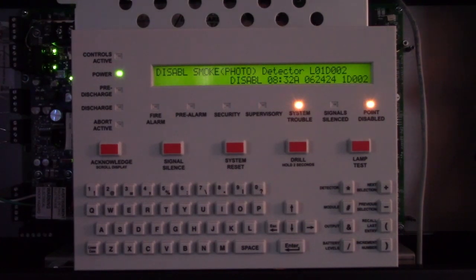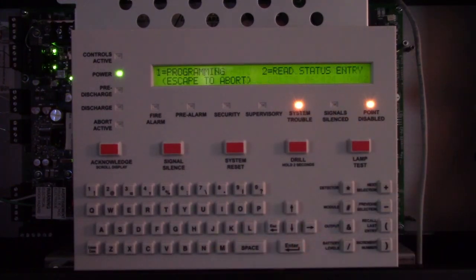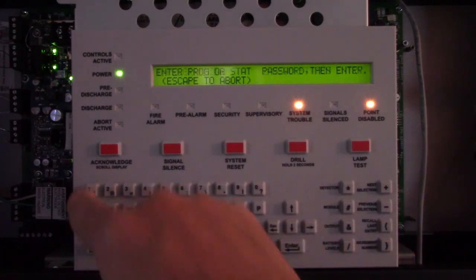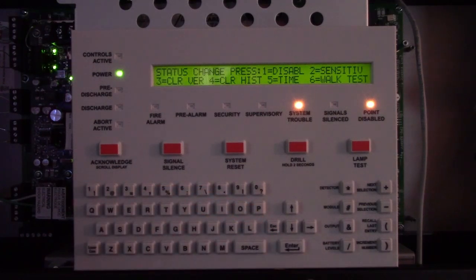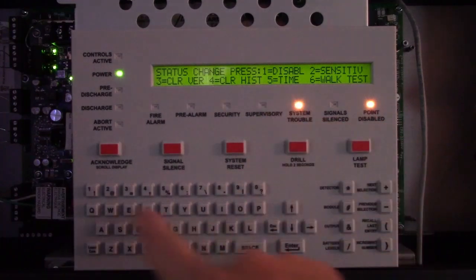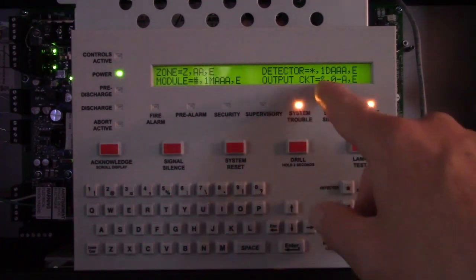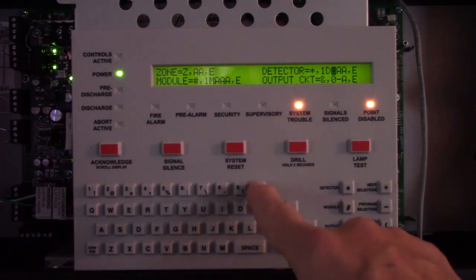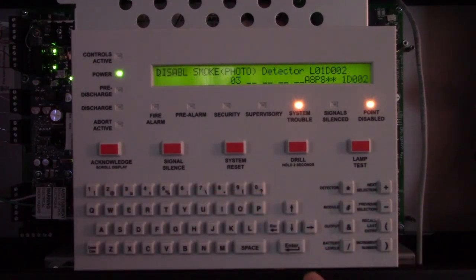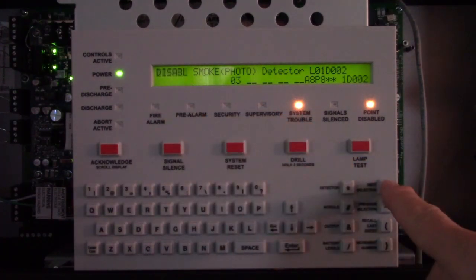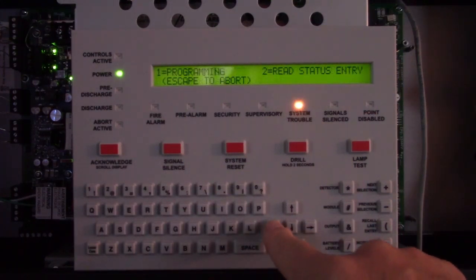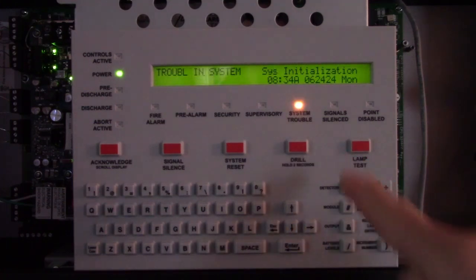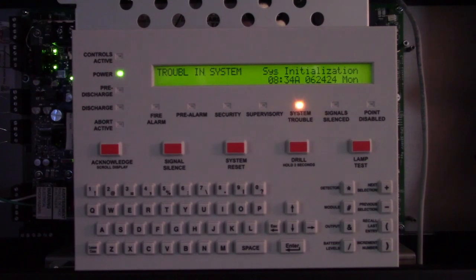Now you've returned — they obtained a lift and you've replaced the smoke detector. Now you need to re-enable that detector. Press Enter, go to programming, enter all ones, go to Disable Device, select detector 002, press Enter. Right now it's disabled — switch it to Enable and press Enter.